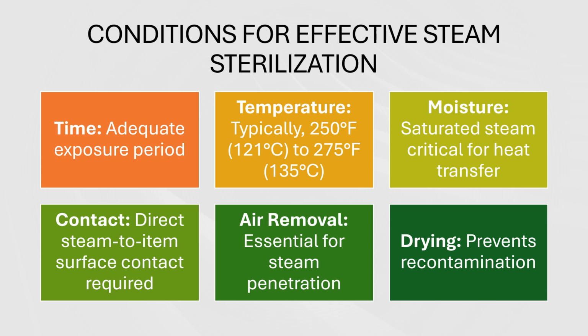The temperature must be within the validated sterilization range. So it's between 250 to 275, depending on what type of sterilizer we are using. Remember, we talked about the moisture. Moisture is critical. This is in the form of saturated steam. It's essential because it transfers heat effectively. Direct contact: this is where the steam and all the surfaces of the items ensure consistent sterilization. Remember, that steam has to stay in direct contact with the devices for the allotted exposure time. So that 4-minute exposure time, that steam has to stay in contact with that device for those 4 minutes.